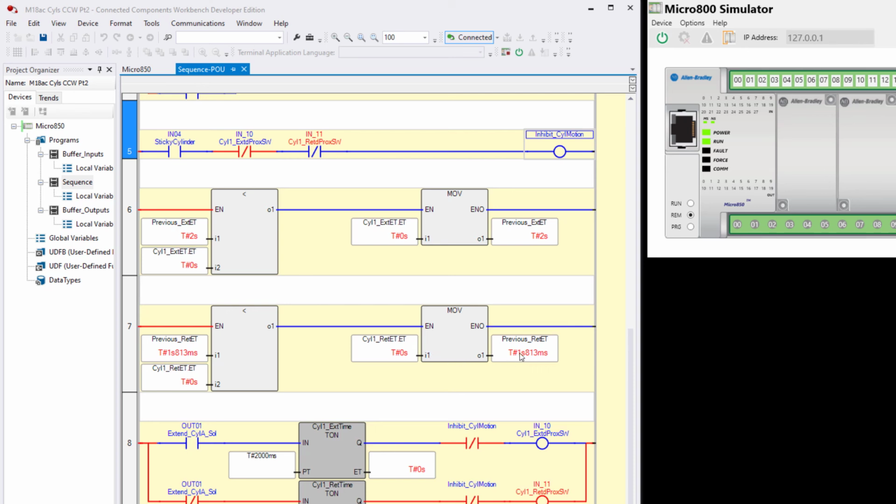So this is a way to capture the current elapsed time for the stroke. Now we know what it is because we're doing it down here. We're simulating it so it's fixed. But if you were to change these values to change the simulated stroke time, these would change to match. However, if you lowered this, shortened the length of time, these would never change. You would have to make these higher in order for this to go above 2 seconds and that above 1.8.